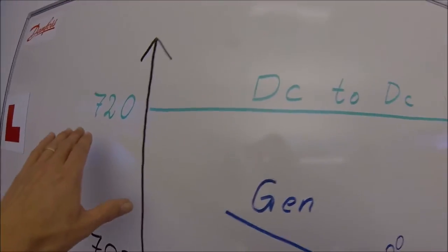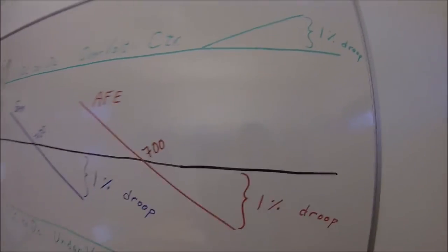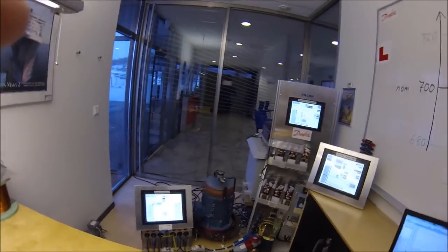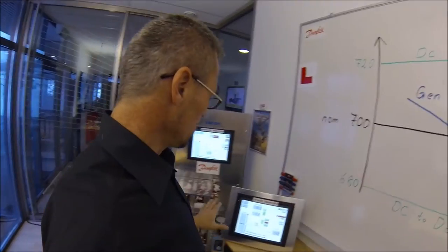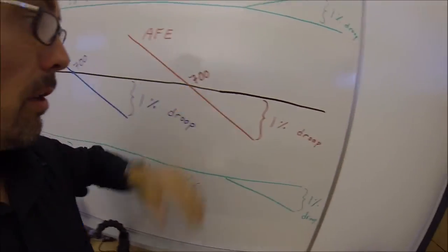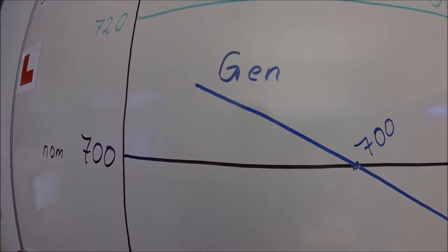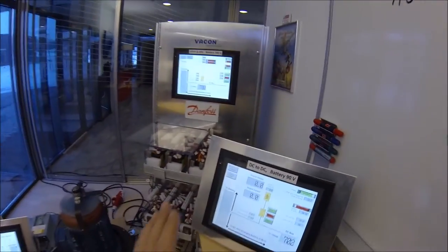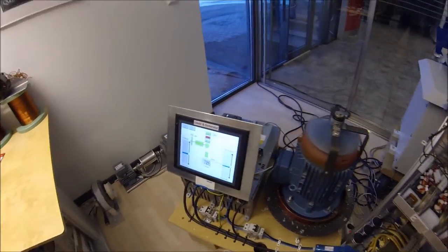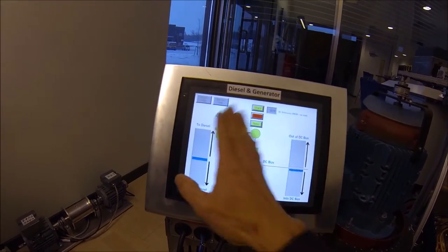Similarly, we have a level for the over voltage controller at 720 volts with a one percent drooping. So this is a system with a calibrated DC level and also a calibrated way of sharing the load on the DC bus. Notice that the load drooping on the DC bus also goes in the regenerative direction — that means if I take power and push it to the diesel engine, the DC voltage will increase and the energy has to go somewhere, so it goes to the ship propeller.